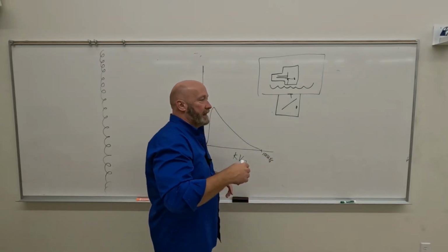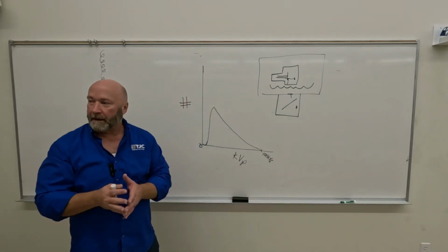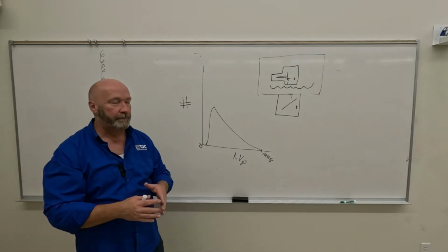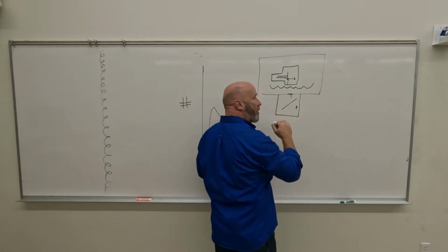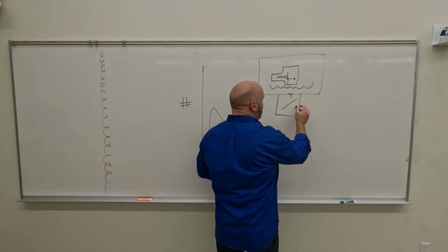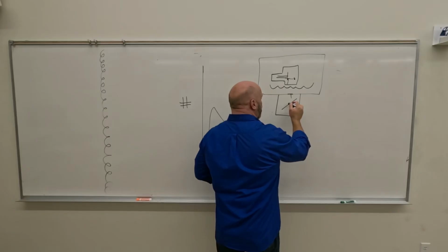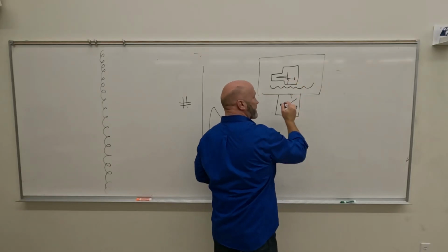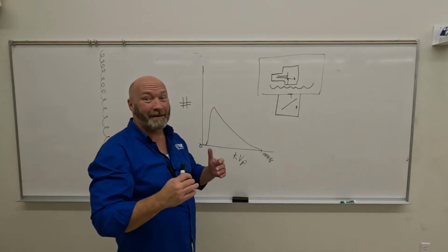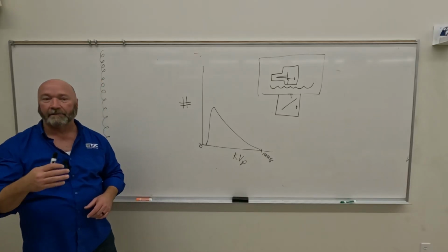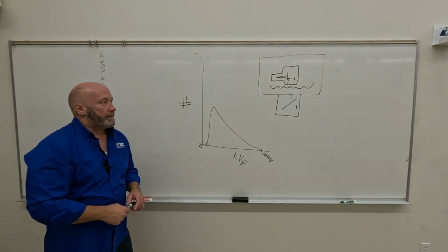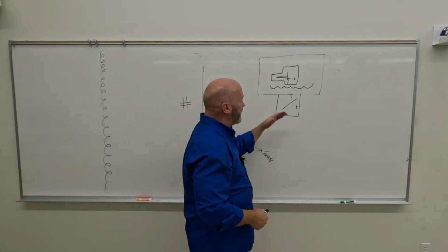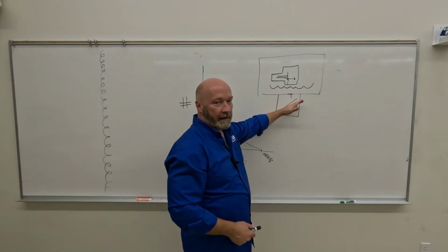Also, because light and X-rays behave the same way and they diverge, the distance between the light and the mirror, and this is never drawn to scale, has to be identical to the distance between the mirror and the focus. Okay, so it's got to be really, really precise to accurately reflect the radiation field. Okay, so again, we've got glass, but we've got glass with what on it?